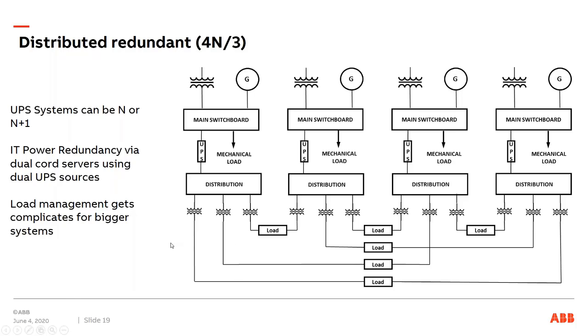The tricky thing with this is that you can balance a load when you first build the data center, but it requires a good amount of effort to make sure that the redundancy is maintained in the system, because each UPS system will not know if it will be overloaded. If somebody sneaks in and installs some IT load in a place where it really shouldn't be, it works as long as all UPSs work. But if one of them fails, one or more of the others may be overloaded.